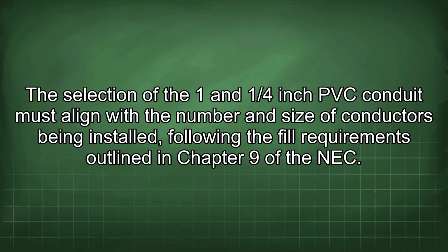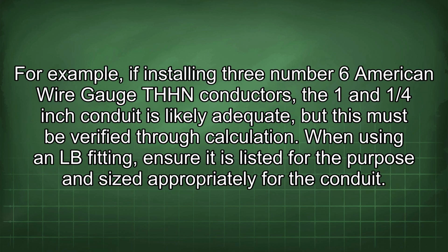The selection of the 1 and 1/4-inch PVC conduit must align with the number and size of conductors being installed, following the fill requirements outlined in Chapter 9 of the NEC. For example, if installing 3 number 6 American wire gauge THHN conductors, the 1 and 1/4-inch conduit is likely adequate, but this must be verified through calculation. When using an LB fitting, ensure it is listed for the purpose and sized appropriately for the conduit.